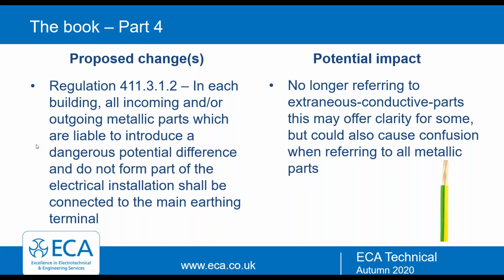The slight issue is they've got rid of the words extraneous conductive part. That's potentially hazardous because that's got its own definition, so it actually means something, and it's already been defined in the book. We don't want to go back to a stage where we are bonding metal window frames, etc.